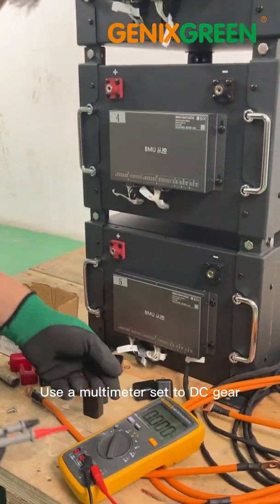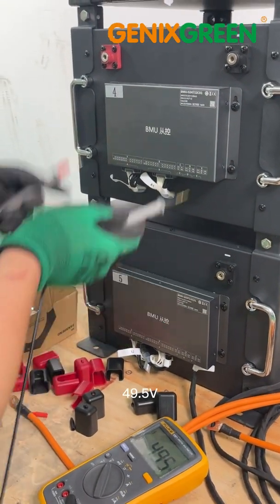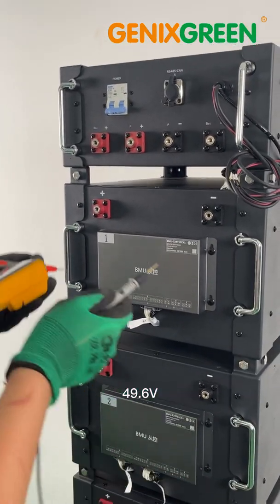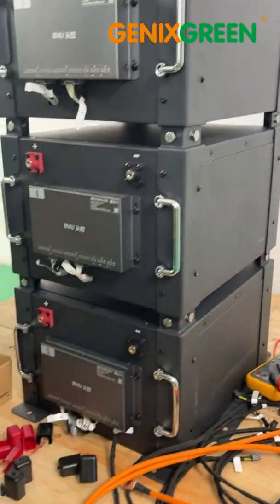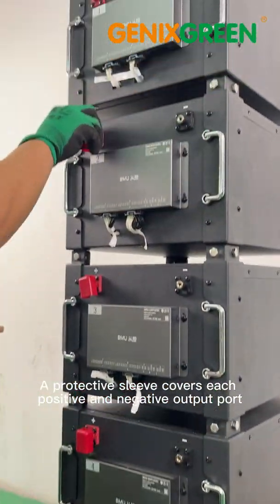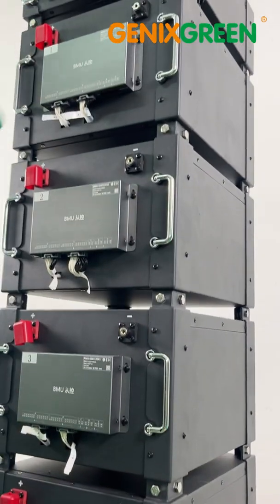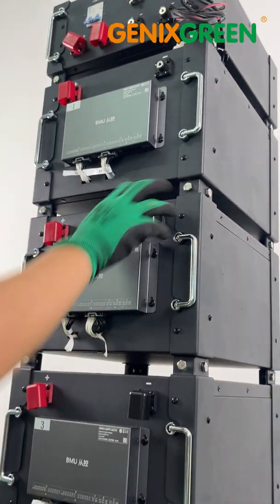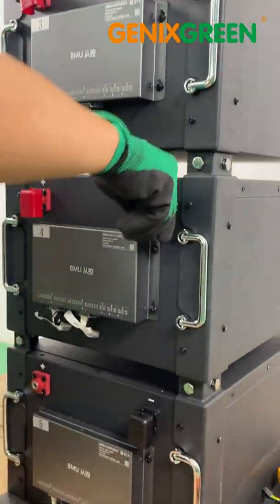Use a multimeter set to DC gear to test each module's voltage. Readings: 49.5V, 49.6V, 49.5V, 49.6V, 49.5V, 50.6V. A protective sleeve covers each positive and negative output port.